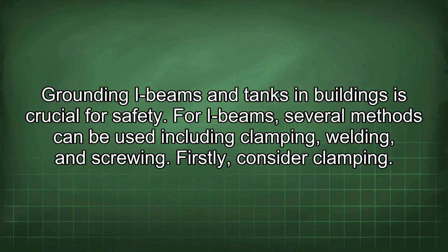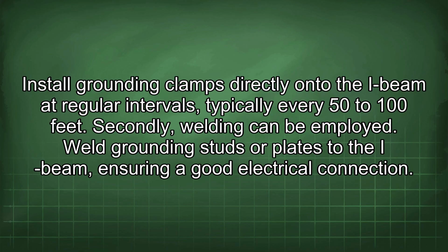Grounding I-beams and tanks in buildings is crucial for safety. For I-beams, several methods can be used, including clamping, welding, and screwing. Firstly, consider clamping. Install grounding clamps directly onto the I-beam at regular intervals, typically every 50 to 100 feet. Secondly, welding can be employed.